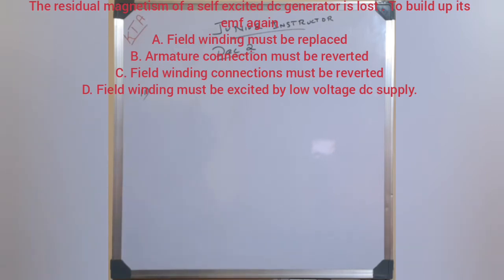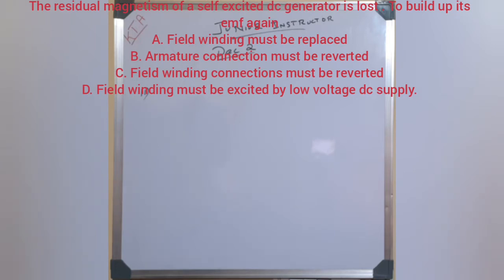A self-excited generator develops EMF using residual magnetism. Residual magnetism is essential for a self-excited generator to build up its EMF. If residual magnetism is lost, the generator cannot develop its EMF on its own.